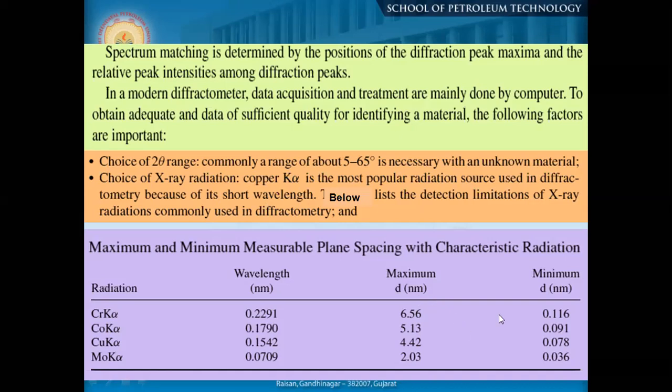Depending on the D spacing of your crystals, you need to select your X-ray source. Depending on the materials, the minimum and maximum D spacing that can be measured differs with different types of X-ray sources. So it's not that you abruptly use certain instruments for doing your data work.